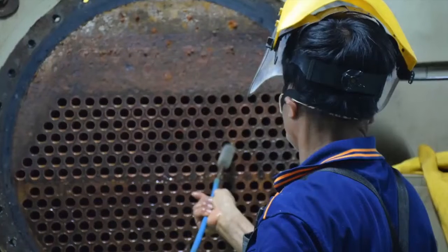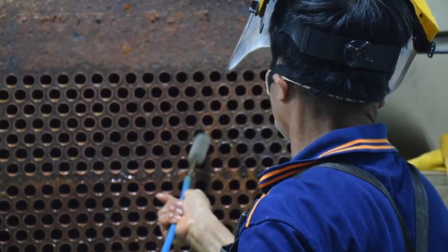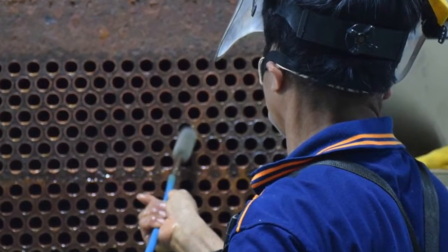The word itself, let's say, reveals its construction. They are exchangers where the two heads can be disassembled and the tubes inside which the fluid flows can be seen. These are straight tubes, so they pass from one head to the other and can be cleaned, brushed with a simple brush. Clearly, the diameter of these tubes depends on the type of fluid that needs to pass through the heat exchange.